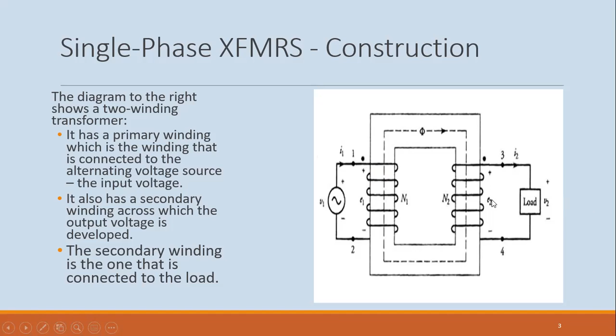Bear in mind that any one of these windings could become primary. Once it's connected to the supply, it becomes a primary winding. So it doesn't have to do with voltage that makes it primary, right? It's where the supply is connected. The primary winding would have the supply voltage connected to it, and the secondary winding would have the load connected to it.